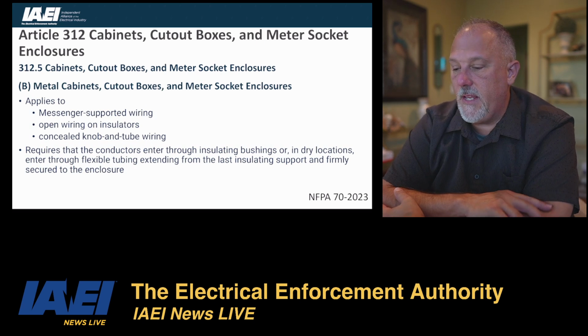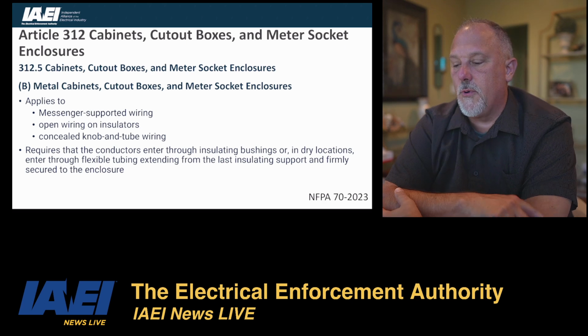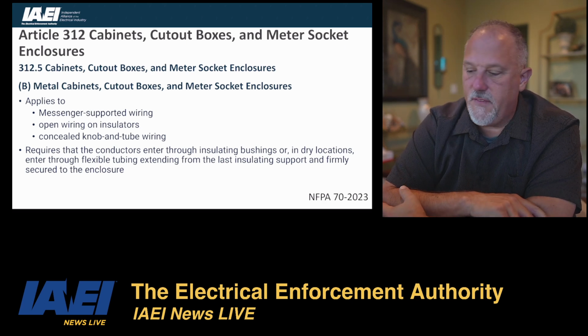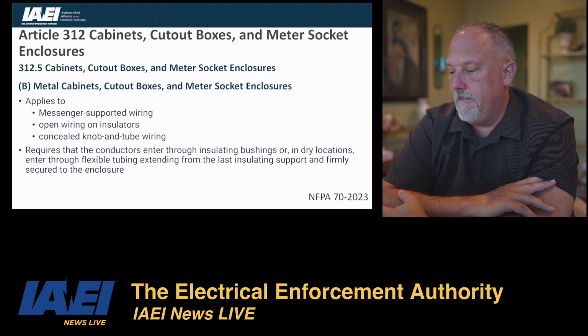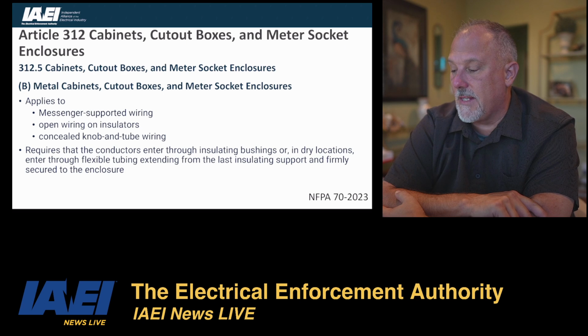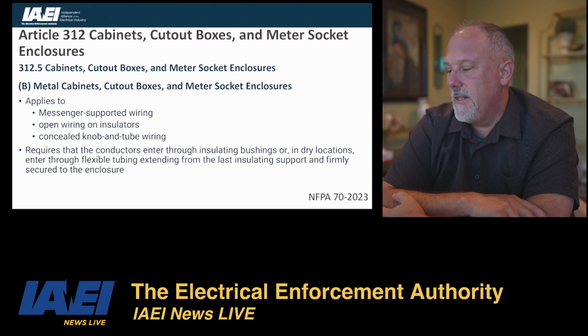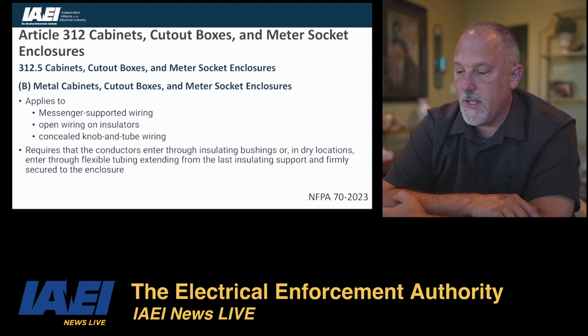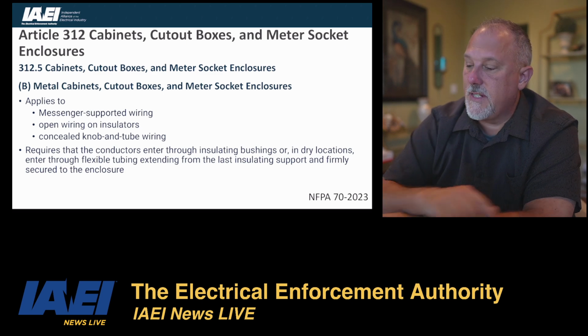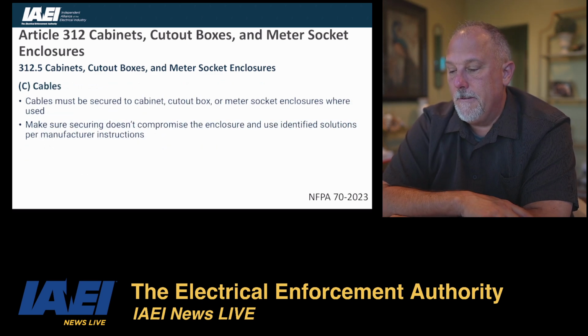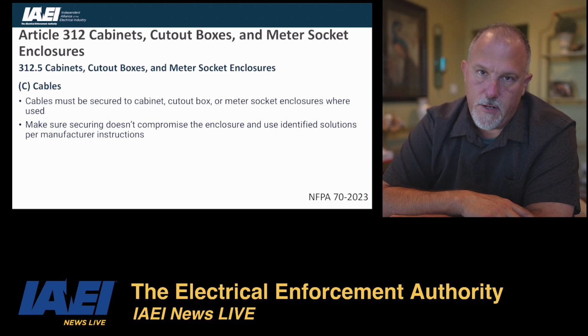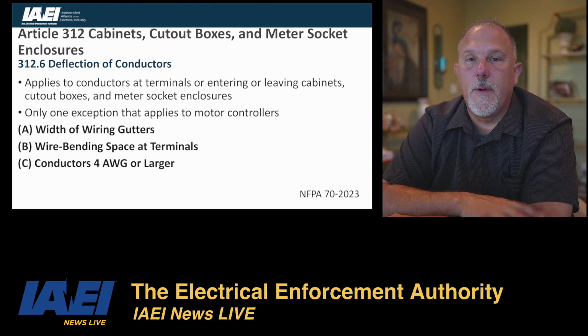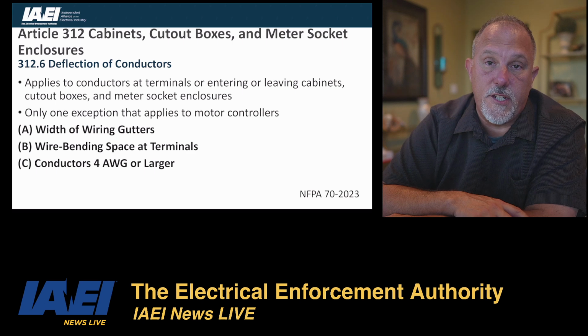And 312.5(B), this is your metal. This applies to your messenger support. This is any of the conductors that are going to be affixed to the outside of that box, or anything that enters through insulating material. You have to enter through an insulated bushing or flexible tubing extended from the last insulated support and firmly secured to the enclosure. So 312.5 in its entirety is going to apply to your application. Your cables have to be secure. Again, you're talking about service conductors here, so you're not going to be running other types of conductors through there. The utility's not going to let you anyway.